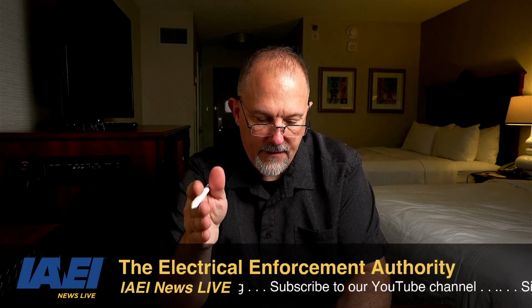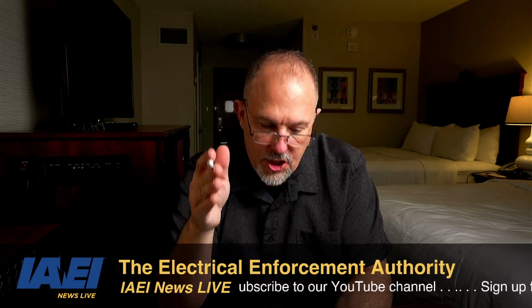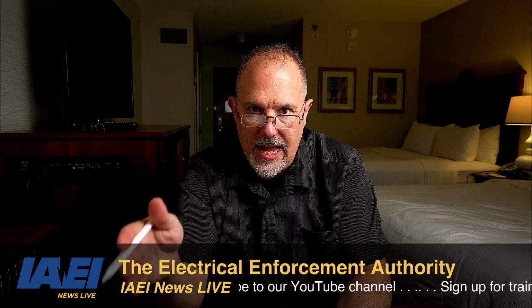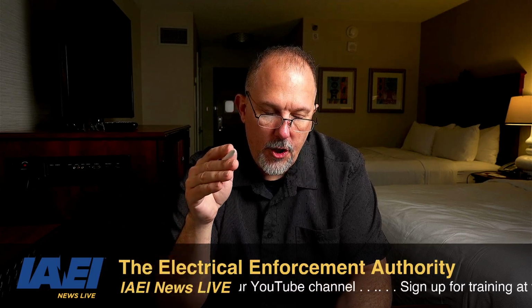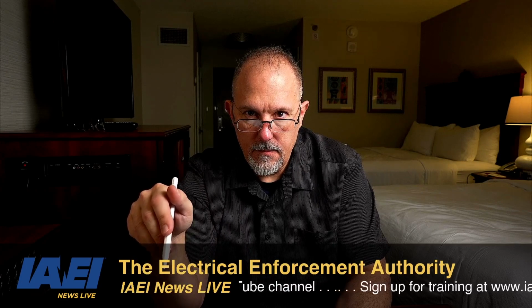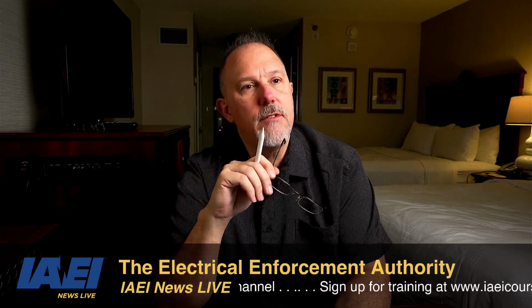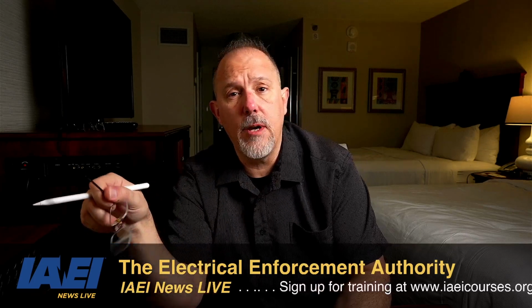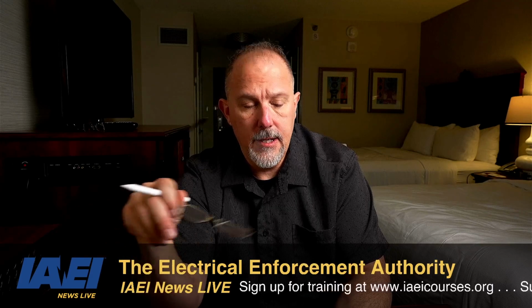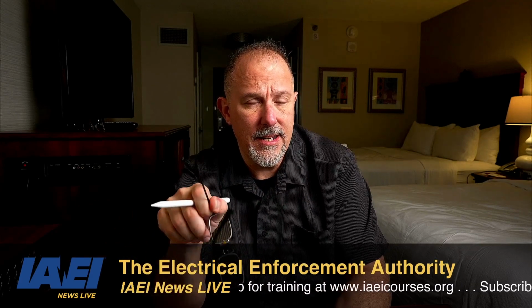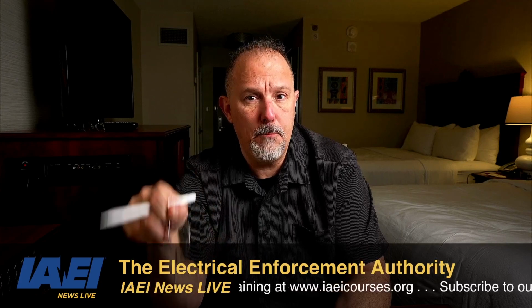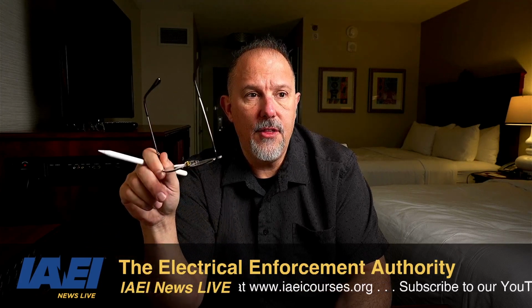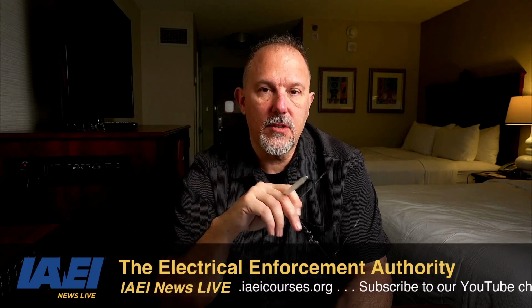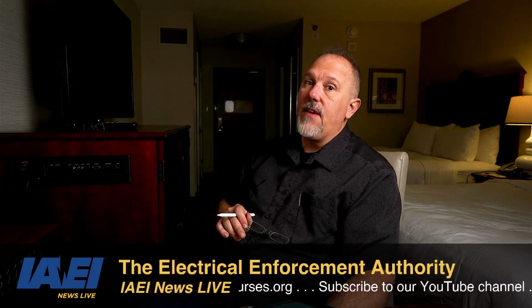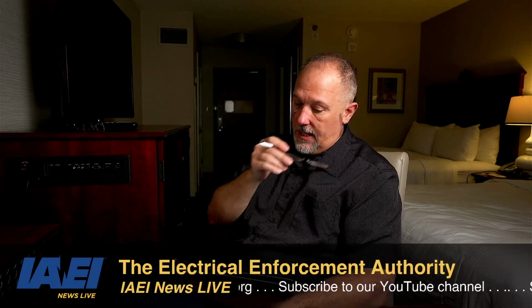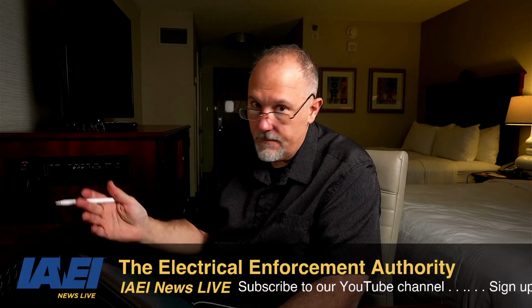But if you have a one-of-a-kind or a custom generator, custom manufactured for whatever reason, you can field label it. So remember, field labeled means you would have a field evaluation body that would come out and review the generator. That's just reviewing the generator, not necessarily the installation, because you have a custom built generator. Those are permitted to be field labeled, and that's going to be looked at by a field evaluation body, which is a defined term again.